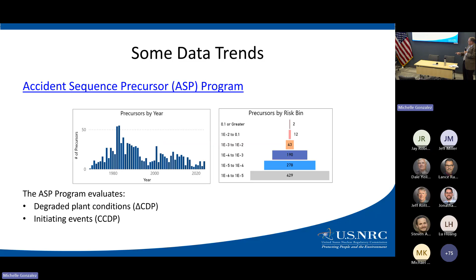The other thing I forgot to mention: the precursor probability threshold we look for is 1E-6. There's a nuance on initiating events where the cutoff may be a bit higher depending on the specific plant. But essentially this is the number of events greater than 1E-6, and we also bin them by their actual risk level.